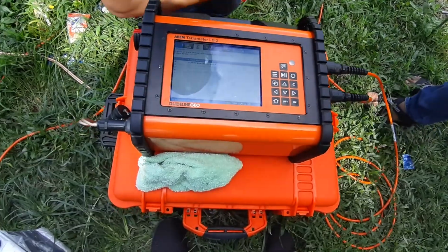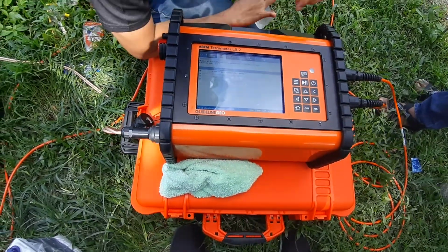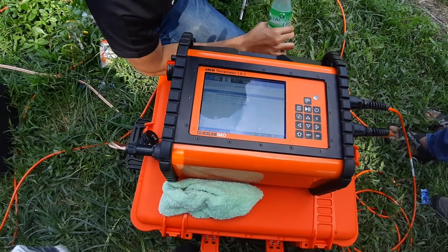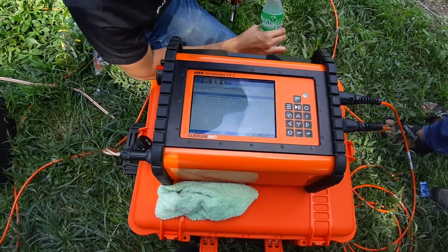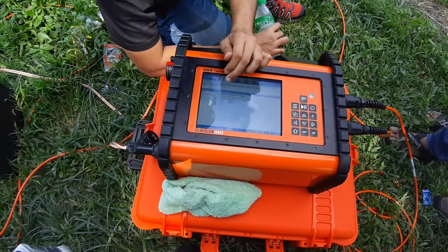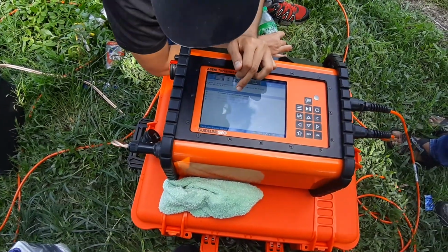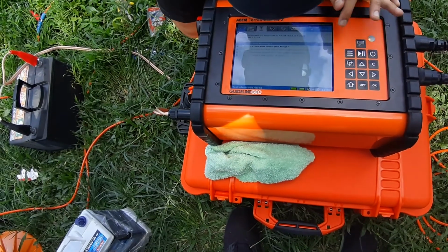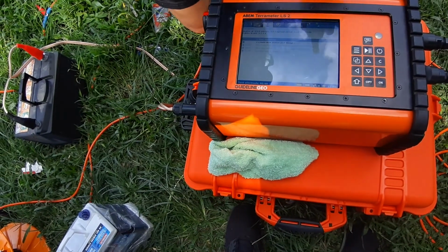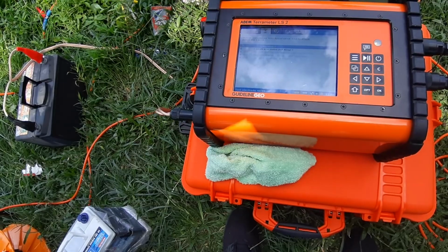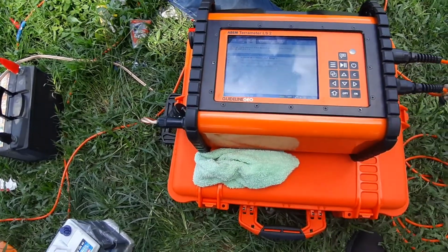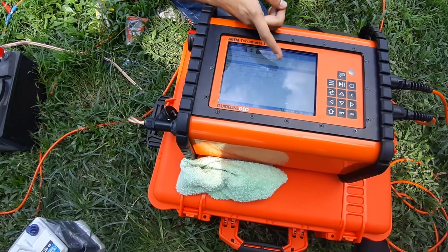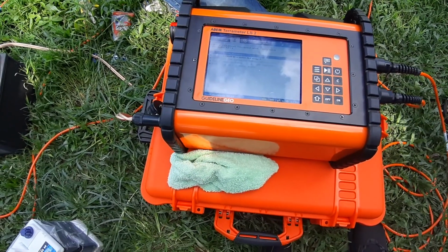Okay. Now it shows that the electrode test failed. Okay, 47. Bad 1, fail 0. Bad means it's still acceptable, but you need to improve the grounding with the ground. That's why we have water here. Fail is 0, so it means everything is connected.